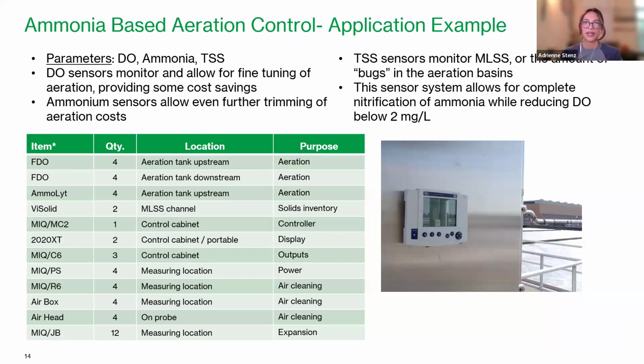This is an ammonia-based aeration control application example. In this case, DO sensors, ammonia sensors, and total suspended solid sensors were used to fine-tune the aeration in their aeration basins. They use the DO sensors to ensure that DO levels never rise above 2 milligrams per liter. And then they use the ammonia sensors to further trim back their aeration. The total suspended solid sensors are used to monitor the MLSS, or mixed liquor suspended solids, which is essentially the amount of microorganisms within the aeration basin that are performing the removal of ammonia.